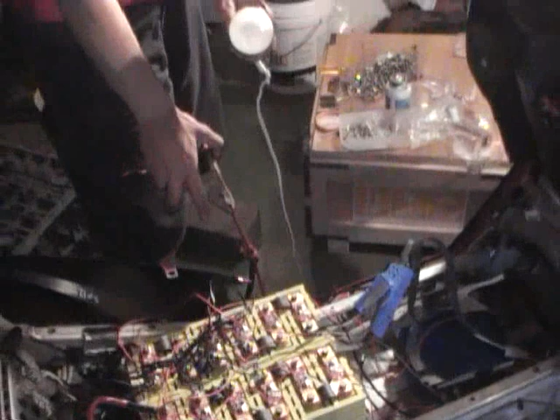Okay, so the final stage is to pre-charge the capacitor bank before we plug it all in. So we've got one side of the alligator clips to the terminal way down in there, connected to this incandescent globe, and then connected there. What will happen is we connect it up, the globe will glow for a moment and then turn off, and once it's off, the capacitors are charged. What will also happen is the BMS will power up. So I'll just connect it up now.